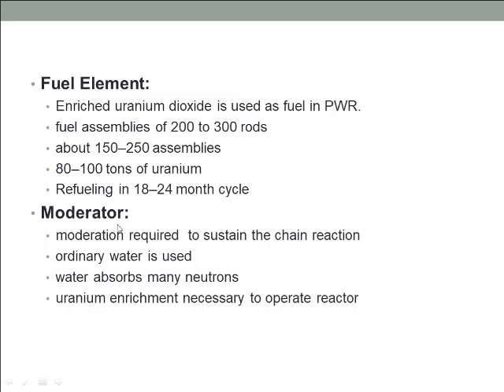The next component is the moderator, like that of the boiling water reactor. A moderator is required in the pressurized water reactor. Fast neutrons must be slowed down in order to interact with the nuclear fuel and sustain the chain reaction. Ordinary water is used as the neutron moderator, where neutrons collide with water molecules and lose their energy, converting fast neutrons to slow neutrons capable of producing fission reactions. Since water absorbs many neutrons, uranium enrichment becomes necessary to operate these reactors.